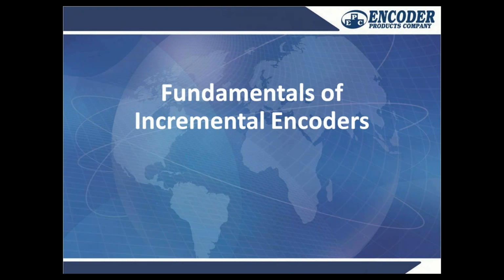Our MTBF math shows all of our models are expected to last 20 years. And encoders, when treated well, made by anybody who makes a quality encoder, you can expect them to last for decades. We get encoders back all the time from the 1970s and 1980s that people are only now looking to replace. So treat them well. Those bearings will last a long time, and there's really nothing else in there that can fail.